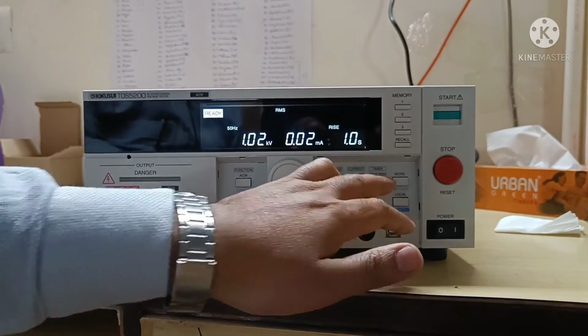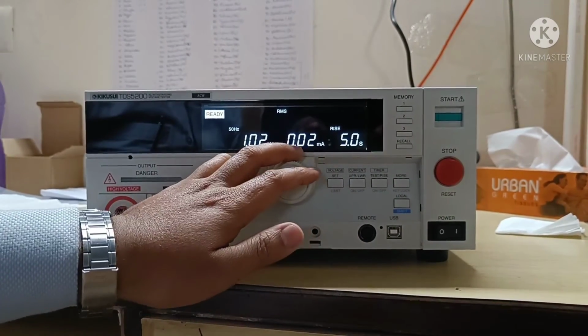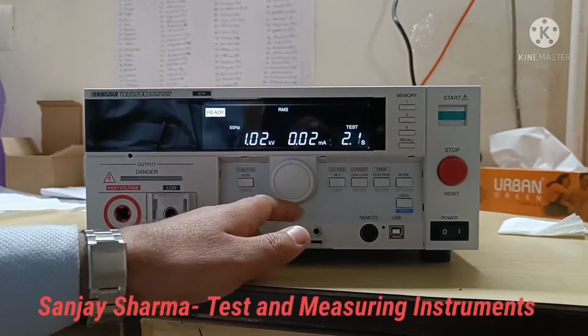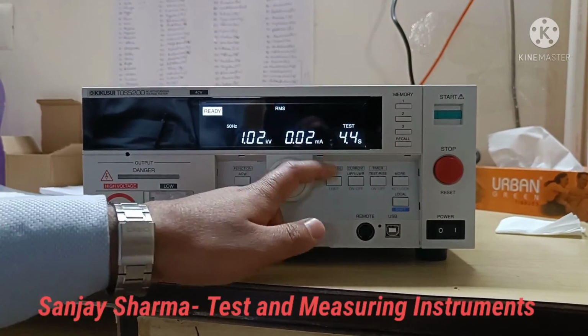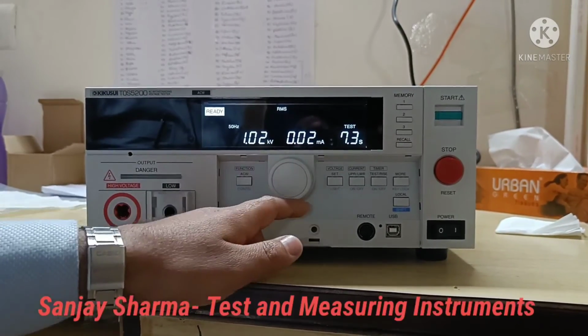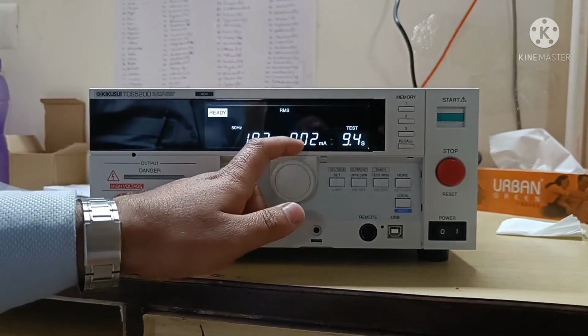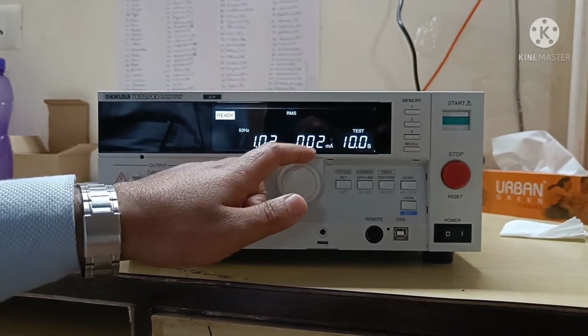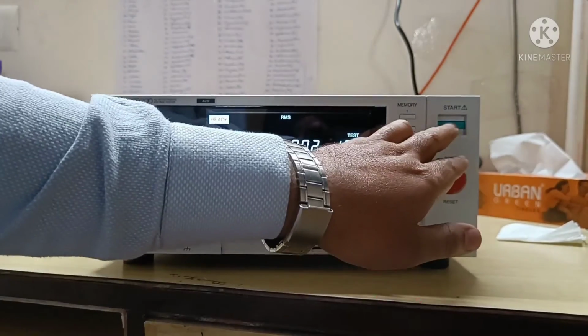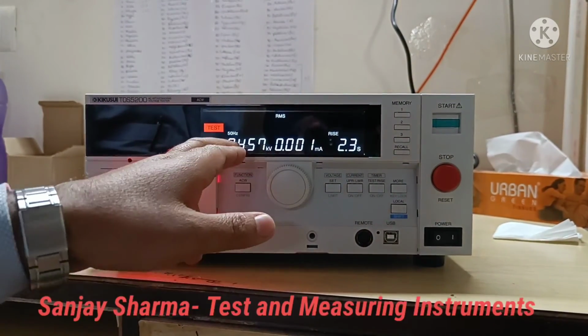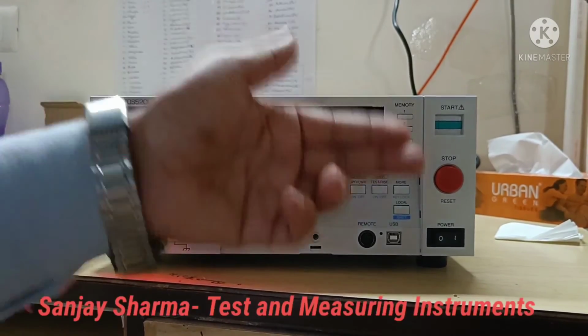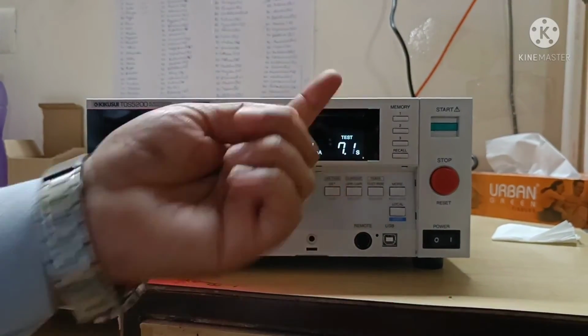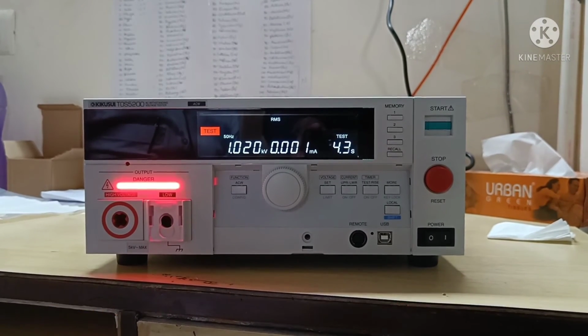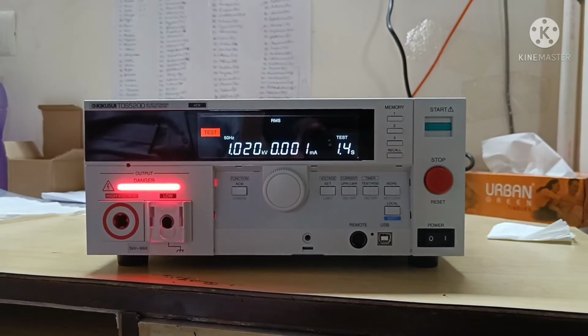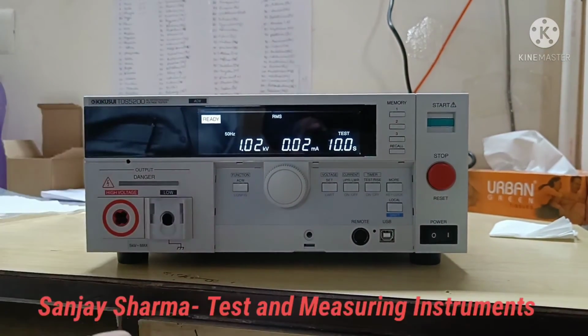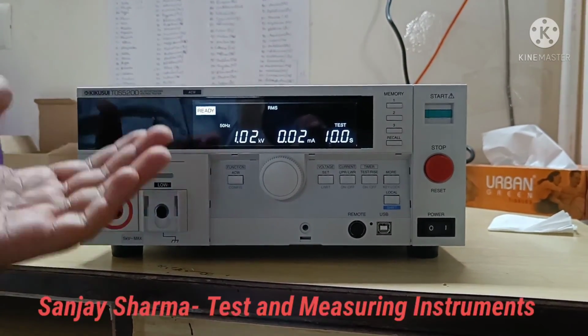So I am going to increase the times: I make the rise time 5 seconds and the test time 10 seconds, so it will be easier to visualize how it performs the test. Here is the test command. This is the rise time, and the voltage will increase according to the rise time. The rise time is completed, and now testing has started for the 10 seconds. So this is how the TOS5200 test is performed.